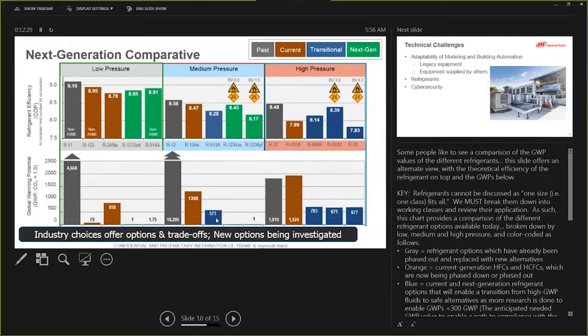There are 2 HFOs that we think are going to be potentially good long-term replacements. Probably the most promising is R-1234ZE. R-1234ZE has a global warming potential of about 1, so it will be an ideal long-term refrigerant. The concern right now with application is that it is considered 2L flammable, though it is on the very, very low extreme of the flammability standpoint. And it does require some pretty significant design changes in this equipment to be able to manufacture equipment economically and sell it to customers at a fair price.